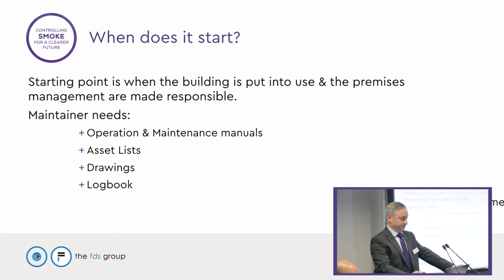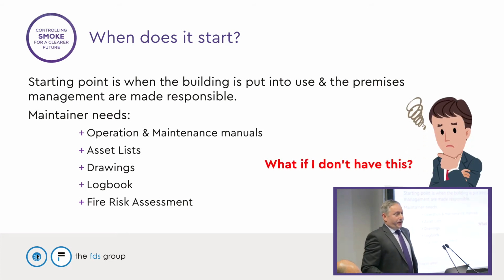If you can't demonstrate you've been maintaining it, the view might be, well, you didn't maintain it without the records to prove so. We also need a fire risk assessment, and this is one of the requirements of the RRO now. So to maintain a building and ensure it's still fit for purpose, has a risk assessment been done, and who's doing that? But often these things don't exist when maintenance companies arrive, and we end up with a bit of a question of, well, what do we do next? We don't have any of this information.